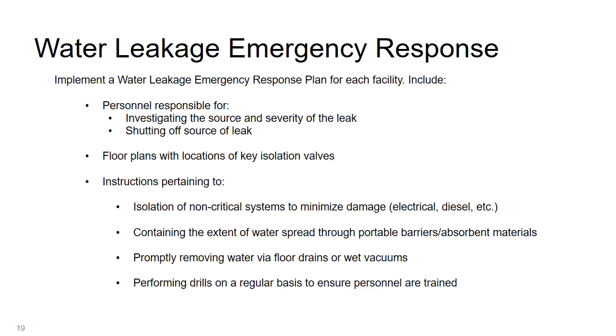Floor plans with locations of key isolation valves will reduce response time. This ties into something that was mentioned earlier, where regular exercising should be performed. If site personnel are familiar with the locations of these critical valves, then the response time can be kept to a minimum. Isolate non-critical systems. In the event of an upset, isolate electrical and diesel systems if they're not needed during the time of the upset. Addressing the leak itself and removing the water.